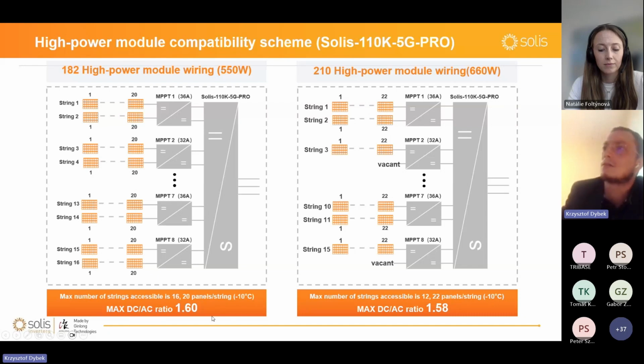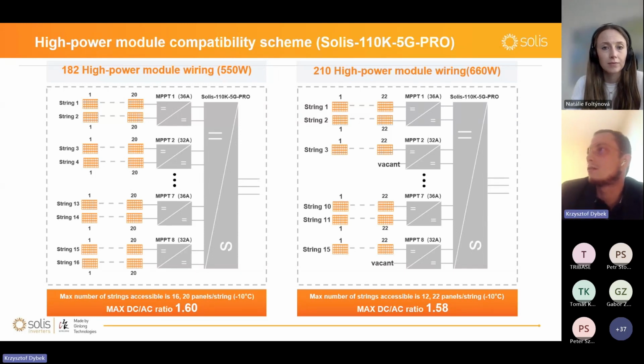Yeah. And the max DC-AC ratio is 1.6, and it is kind of similar, 1.6 in general, but you can of course exceed something here. It is not very strict, but after you exceed this value, you need to be extremely careful with matching maximum voltage per MPPT and maximum short circuit current per MPPT, because of course short circuit current is bigger.